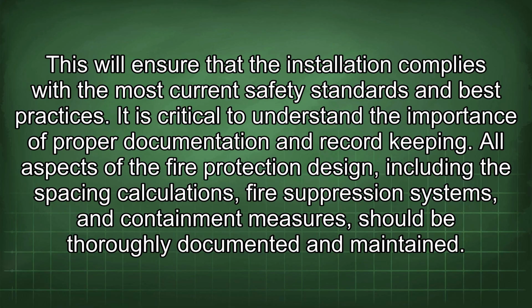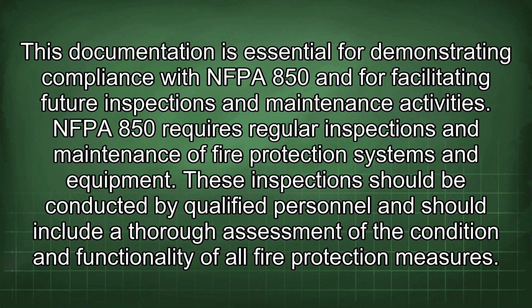It is critical to understand the importance of proper documentation and record keeping. All aspects of the fire protection design, including the spacing calculations, fire suppression systems, and containment measures, should be thoroughly documented and maintained. This documentation is essential for demonstrating compliance with NFPA 850 and for facilitating future inspections and maintenance activities. NFPA 850 requires regular inspections and maintenance of fire protection systems and equipment.